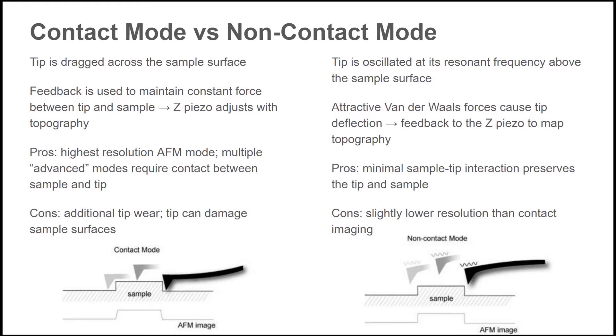In a non-contact measurement, the tip is oscillated very quickly. Non-contact tips are stiffer than contact tips and act more like springs — they have a resonant frequency. As the tip comes close to the sample, van der Waals forces cause deflection, which will feed back to the z-piezo and map out the topography. Because the tip is oscillating, it has less interaction with the sample and there will be less overall wear. This is why non-contact measurements are generally preferred over contact measurements.